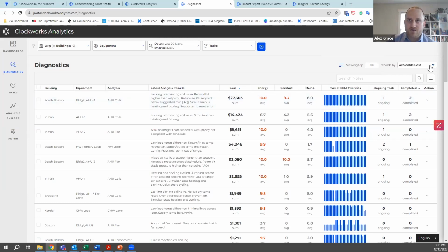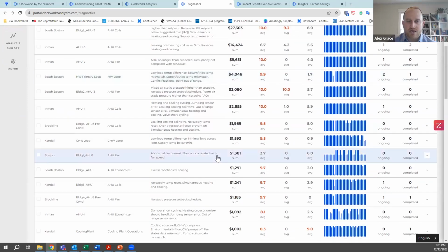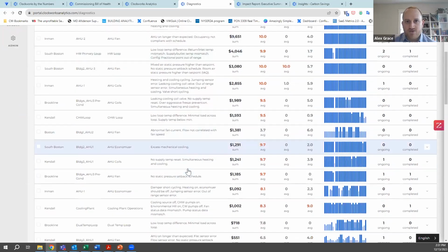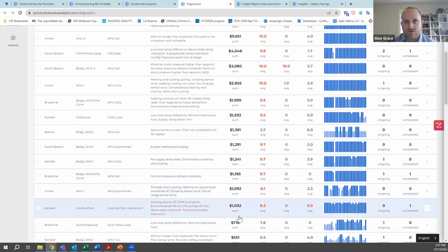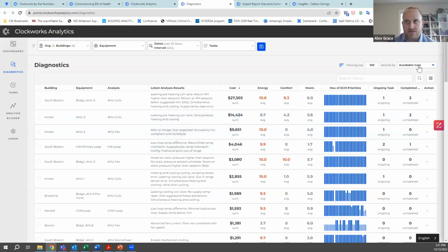I can also resort this list by other priorities. Right now we're looking by energy. We're seeing leaking valves, simultaneous heating and cooling, loop low delta T's, issues on the cooling side, abnormal fan current, excess mechanical cooling on an economizer—all sorts of issues relative to high energy, excess energy consumption.